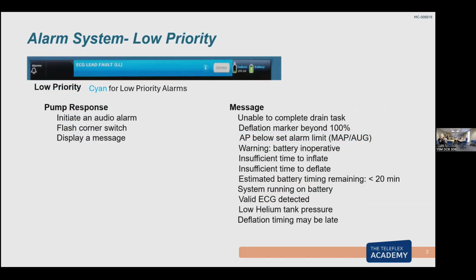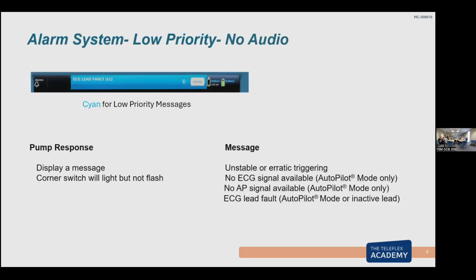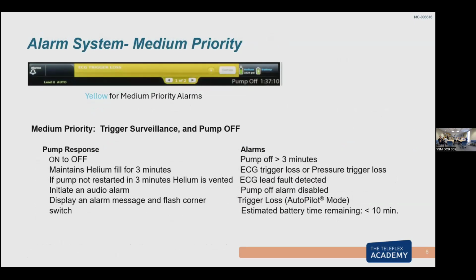So again, a blue alarm is just a message alarm. The pump is still pumping. Low helium tank, they popped off a lead, and it tells you what lead. In the message bar, it actually tells you what the troubleshooting would be, so it's not something I have to go look up. It's right there on the screen. For some further yellow ones, the pump does stop pumping. It's beeping at you. This is usually because I've been in standby too long, or I have no signals for the pump to work with. I've got to have an ECG or arterial pressure on the screen for the pump to work.